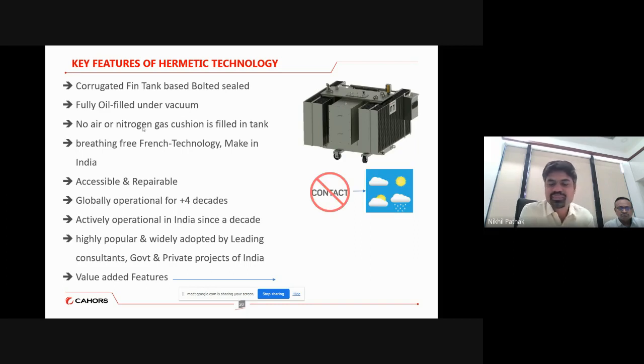So here you can see there is no conservator in the transformer, and there is no breathing element, because we say that it's a breathing-free technology. So it is restricting the contact of the oil with the external atmospheric condition. Whether it is summer, rainy season, or winter season, in all atmospheric and weather conditions, the transformer sustains, and it gives the concept of no contact with the external atmosphere. By doing that, we are avoiding the oxidation of oil, and that is the reason the oil oxidation is restricted and the BDV lowering goes very slow.